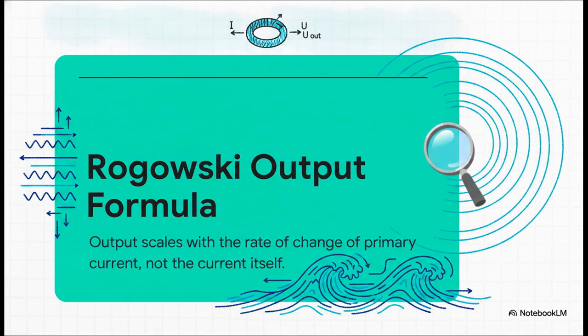It shows that the secondary output voltage, U out, equals a mutual inductance constant, M, multiplied by di/dt. Now, in plain engineering terms, that just means the voltage output is directly proportional to the rate of change of the primary current, not the raw current itself. This specific trick of physics is exactly what prevents the coil from ever saturating. It really doesn't matter if the current spikes instantly. The output simply scales with the rate of that change, keeping your data incredibly accurate.